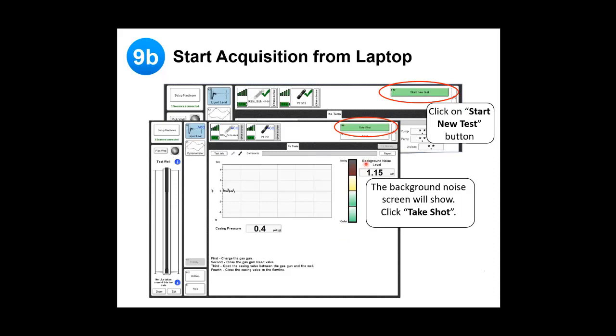Now, if we're going to start the acquisition from a laptop, rather than pushing the acquire button on the gun, we're going to be in TAM and we're going to click on the Start New Test button. This serves the same function as clicking the acquire button. From Start New Test, as we've seen, once we charge up the capacitor to the proper voltage and open the solenoid, the Take Shot button will be displayed. You can click Take Shot, and that will initiate the acoustic pulse.